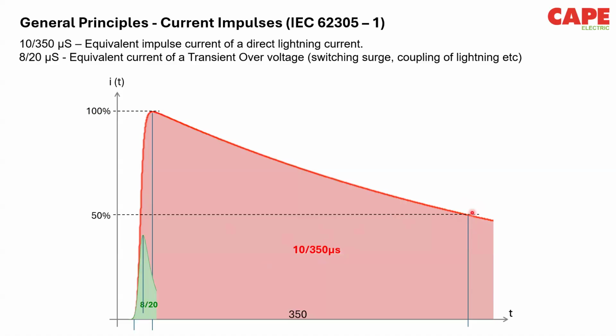And parallelly, you have 8 by 20, which is for indirect lightning surges. Same concept: at 8 microseconds it will reach the peak, and at 20 microseconds it will reach the 50% mark. Now, this wave shape is used to define how an SPD is tested and erected at your building.